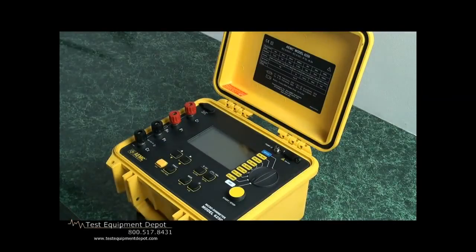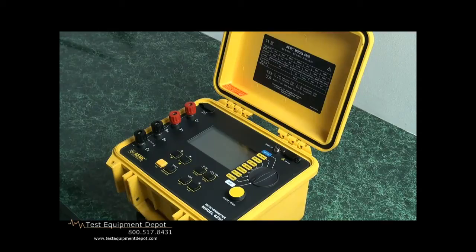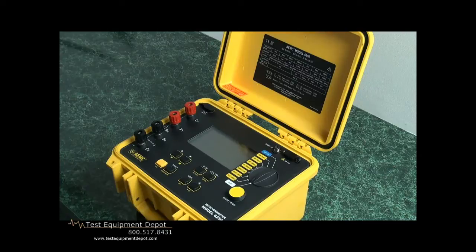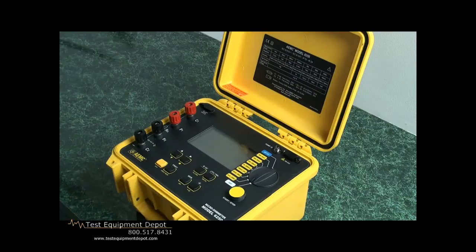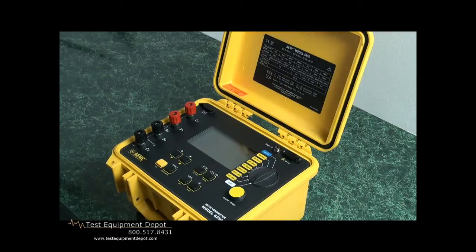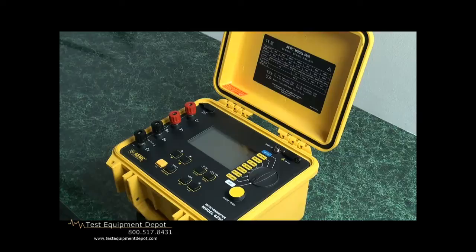The AEMC Model 6250 micro ohmmeter is unique in that it can measure out to 0.1 micro ohm. That is extremely sensitive and probably perhaps the best in the industry. It can measure up to 2,500 ohms, so it does have a broad range, although normally we'll be measuring down into the very low ohm resistance.